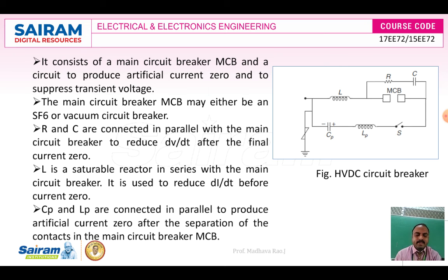Here the MCB can be a vacuum circuit breaker or an SF6 circuit breaker. R and C are connected in parallel with the MCB. Why? To reduce dV by dt after final current zero. After final current zero, some voltage will be there, with its dV by dt. If you want to reduce it, we have to connect R and C in parallel to the MCB, right? And L is connected in series with the MCB to reduce dI by dt before current zero. That is why R, C and L are connected.